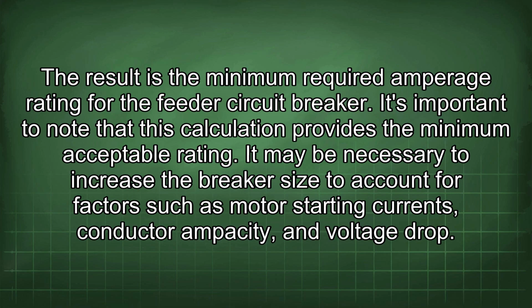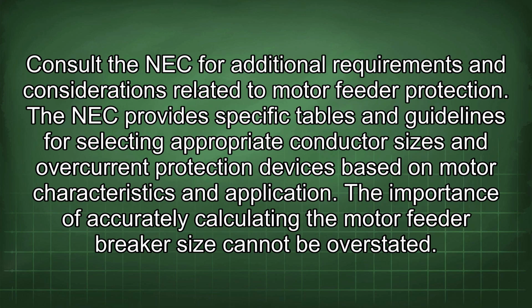It's important to note that this calculation provides the minimum acceptable rating. It may be necessary to increase the breaker size to account for factors such as motor starting currents, conductor ampacity, and voltage drop. Consult the NEC for additional requirements and considerations related to motor feeder protection. The NEC provides specific tables and guidelines for selecting appropriate conductor sizes and overcurrent protection devices based on motor characteristics and application. The importance of accurately calculating the motor feeder breaker size cannot be overstated.